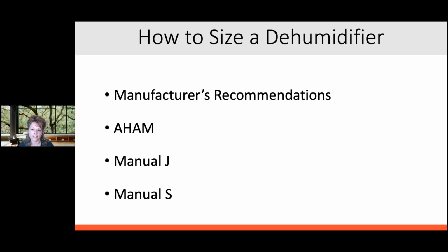So how do you size a dehumidifier? We have manufacturers' recommendations, and you have to be very careful with that. There is no governing body that determines what I can claim per square footage for my dehumidifiers versus my competitor. I might say 1,800 square feet for our 70 pint, and my competitor can say they can do 3,000 square feet with their 70 pint. There's nobody determining what the claims can be. Again, we are very conservative in our numbers. You also have AHAM, Manual J, and Manual S, and we'll look at those quickly.